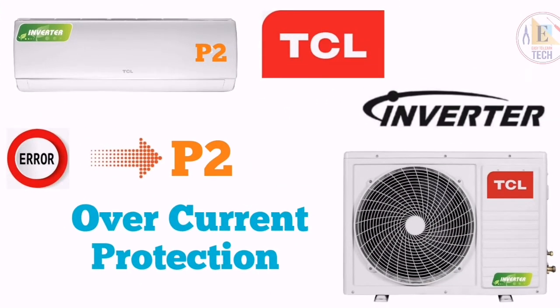When you see error P2, it means overcurrent protection in your outdoor unit. First of all, you have to check the outdoor fan motor if it is stopped due to overheat protection or damage, and if it is not damaged, then you have to check your capacitor. And if your capacitor is also not damaged, then you have to check your intelligent power module if it is damaged or not. And if it is damaged, you have to replace it and your unit will be in working condition.